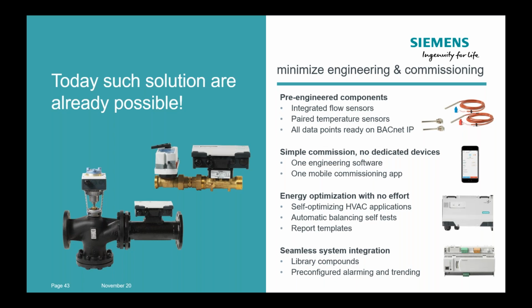So the intelligent valve solutions we see on the market, they are really a perfect package usually. They are pre-engineered, they integrate the flow sensor with the right resolution, with a wide measuring range. They have the right control valves pre-engineered here, and all the BACnet points into the network. You can easily integrate this with predefined function blocks into the automation level of the network. And also here we have, for the technicians, a really easy engineering software available. On the one hand, an easy tool in a mobile app for the presetting locally and for the troubleshooting locally. On the other hand, an engineering software if you integrate this into the automation level network with these predefined function blocks.